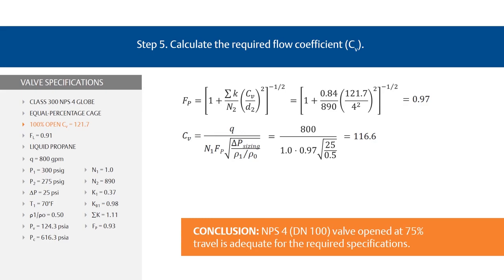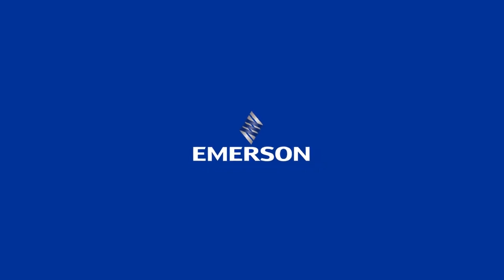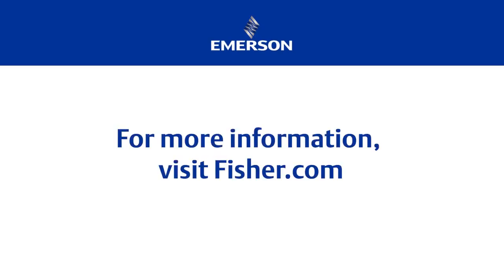The conclusion is that an NPS4 valve opened to about 75% of total travel should be adequate for the required specifications. So that's the process for sizing a valve for liquid flow.